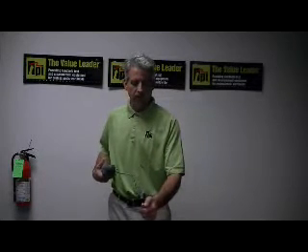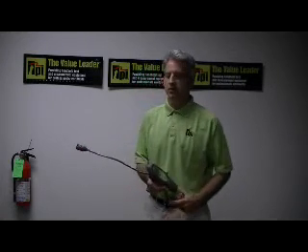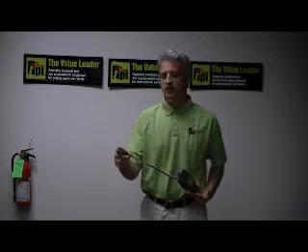In this particular instance, I'm going to use a butane lighter and shoot the instrument with some butane. You hear the alarm sound and you also see the visual indicator light up in the tip of the instrument.